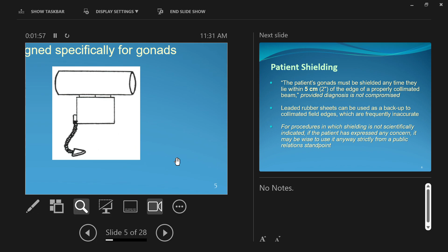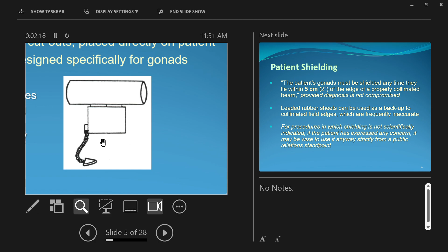And there are also shadow shields. Shadow shields cast a shadow of the shield onto the patient, and they actually hang off of the x-ray tube. This is a crude drawing of a shadow shield. That little triangle hanging off the bottom is the shield. We have one on our x-ray tube in here, so next time you're in the x-ray room, take a look. They don't touch the patient. They just hang underneath the x-ray tube, and that little triangular piece of lead, you can bring it in, and it just blocks part of the x-ray beam, and you cast a shadow of what you want blocked down onto the patient. It's a way of blocking the beam without actually having the shield touch the patient.